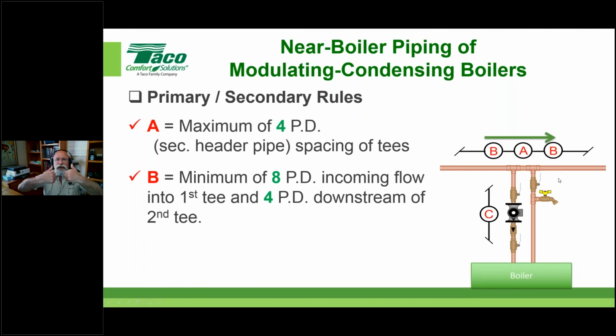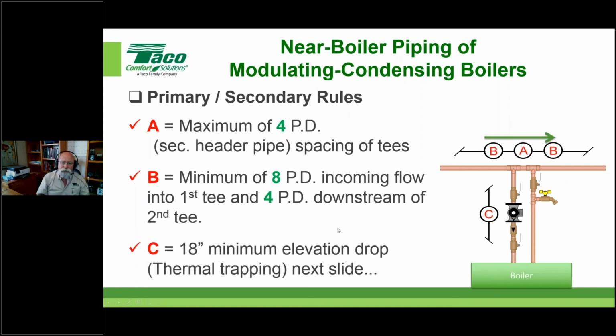Again, conceptually, 2 T's in the middle of a nice long piece of pipe. Understand that concept, you'll stay out of trouble. The C note here is just actually having hotter water higher than the cooler water, so you get some thermal trapping going on, and that's kind of a throwback to the variable speed injection mixing. We're not going to spend time on the C note, but just remember that the hotter water needs to stay higher than the cooler water in mixing primary secondary.